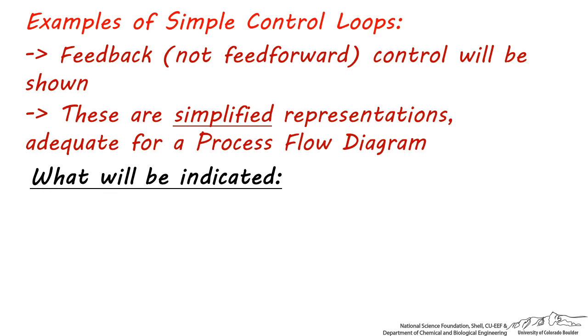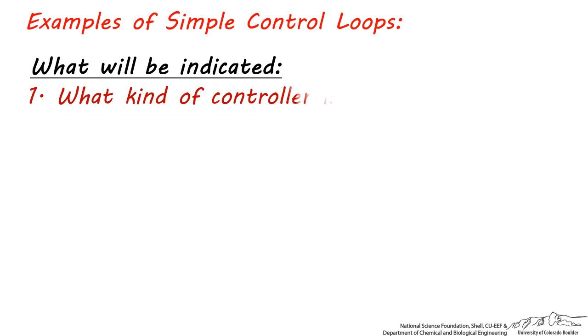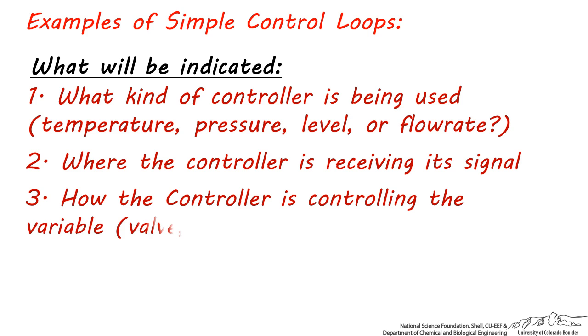Since we're specifying simple control loops, we'll only be indicating three things: what kind of controller is being used, where the controller is receiving its signal, and how the controller is controlling the variable, whether it's by opening and closing a valve, varying the power to a pump or compressor motor, or changing the flow rate of an inlet stream.